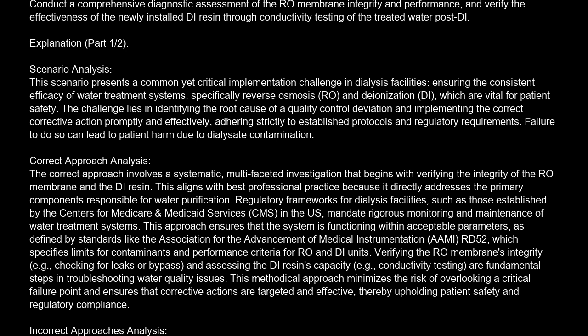Explanation. Scenario analysis: this scenario presents a common yet critical implementation challenge in dialysis facilities, ensuring the consistent efficacy of water treatment systems, specifically reverse osmosis and deionization, which are vital for patient safety. The challenge lies in identifying the root cause of a quality control deviation and implementing the correct corrective action promptly and effectively, adhering strictly to established protocols and regulatory requirements. Failure to do so can lead to patient harm due to dialysate contamination.